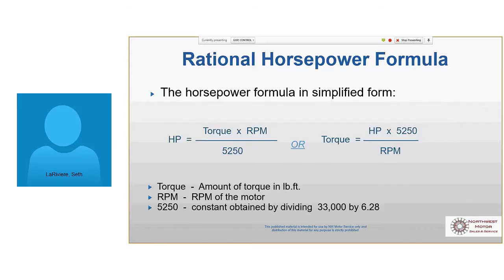This is another useful formula. If you want to know what your horsepower is, you can take, well, torque is usually an unknown, so usually you're working this way. If you're wanting to solve for torque, take the horsepower times 5250 divided by the RPM, and that equals torque.